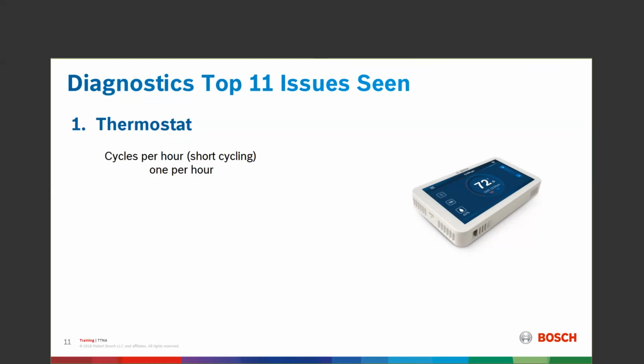They have an economy mode. Typically about 9 o'clock at night, they set the temperature back in the home at a 10 degree setback or droop. A 10-degree droop tends to make complaints that the house is cold at night. The heat pump cannot keep up in the evening hours. It can keep up if it's not running, for sure. And the last one is it has a momentary droop of the 24 volt on the Y to C terminal at the compressor section. It does seem to appear every 15 to 17 minutes we lose our 24 volt signal for about 3 seconds.